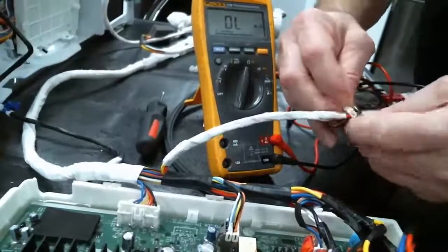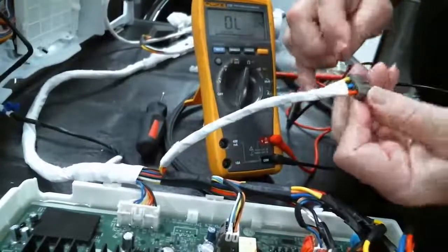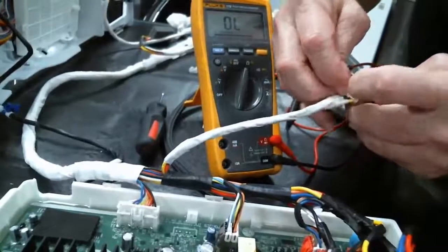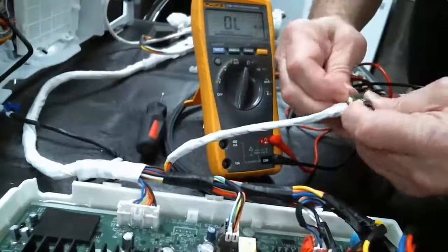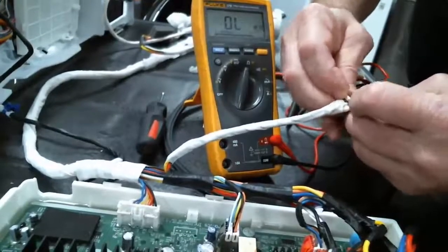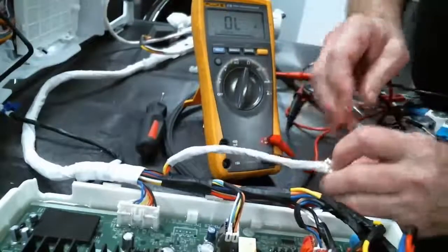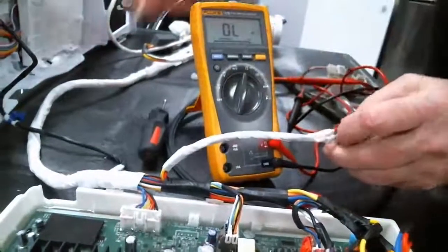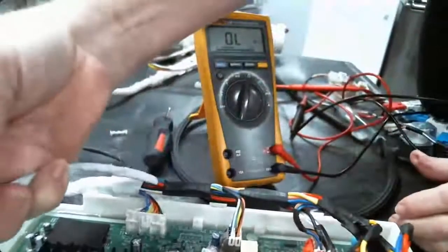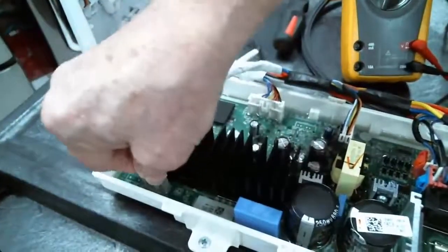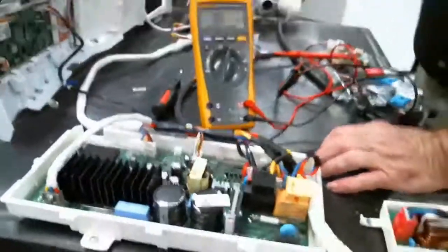Now, normally we do not have to check for voltage at the stator, but there are situations where we're getting the LE error code—let me tell you what that stands for, I'll put this clip in a bit later. LE error code means I don't see rotation on the motor when I'm supposed to. This could be a situation where your inverter is not sending power down to that motor. You can check voltage there.